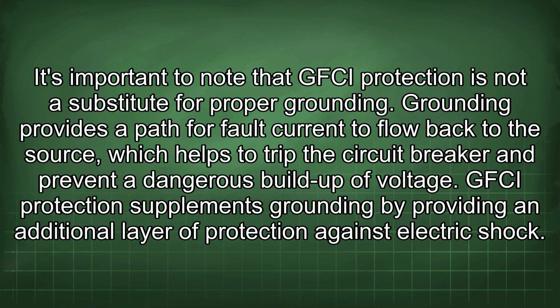It's important to note that GFCI protection is not a substitute for proper grounding. Grounding provides a path for fault current to flow back to the source, which helps to trip the circuit breaker and prevent a dangerous build-up of voltage. GFCI protection supplements grounding by providing an additional layer of protection against electric shock.